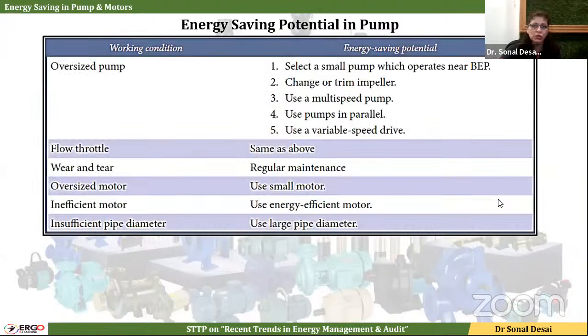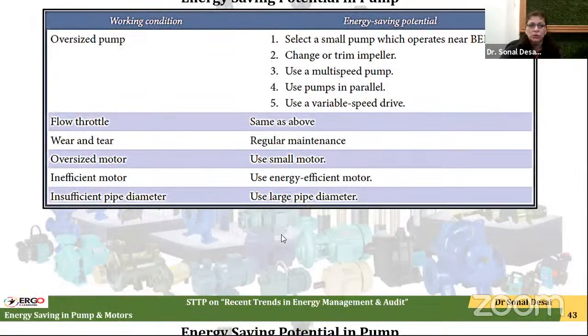Again, there is one more slide which shows how to optimize the pump from an energy efficiency point of view. That is, if an oversized pump is there, then go with multiple pumps, change the impeller, or select a smaller pump so that it operates near its efficiency point, or go with a variable speed drive. If there is flow throttling, the same applications apply. If there is wear and tear, go for regular maintenance. If an oversized motor is there, go with a smaller one. If an inefficient motor is there, go with an IE1, IE2 motor. If insufficient pipe diameter is there, then enlarge the pipe diameters.